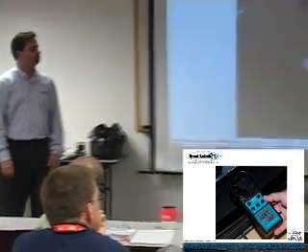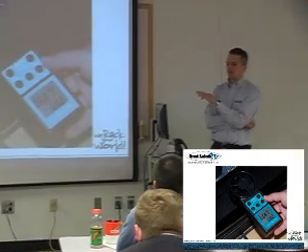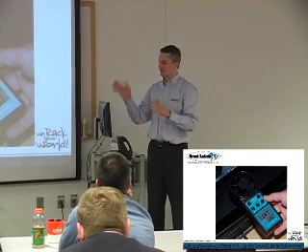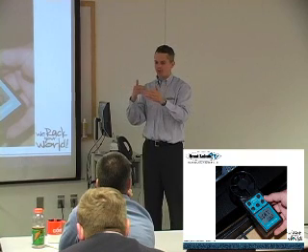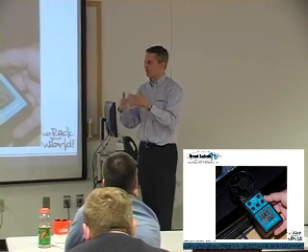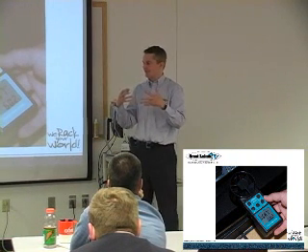One of the things that Bill hit on earlier in the PowerPoint is the temperature differential that occurs between your mesh. You have the 3 to 5 degree barrier. It will be warmer inside of the enclosure.